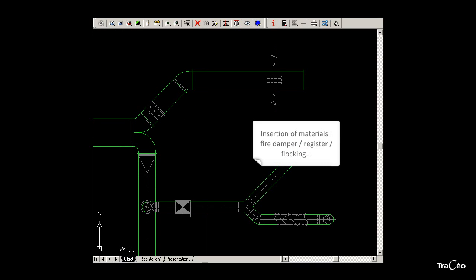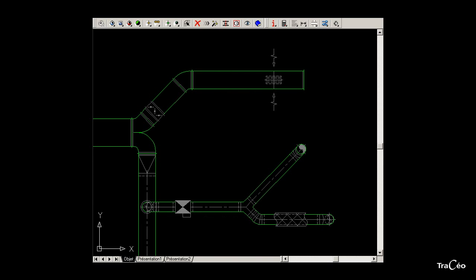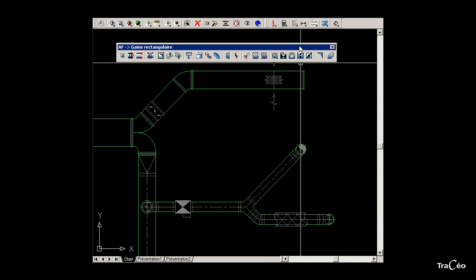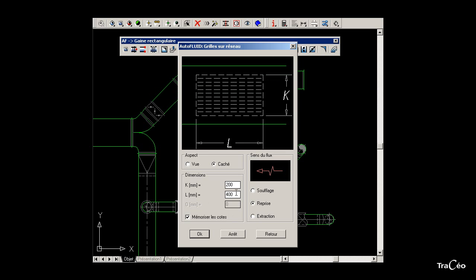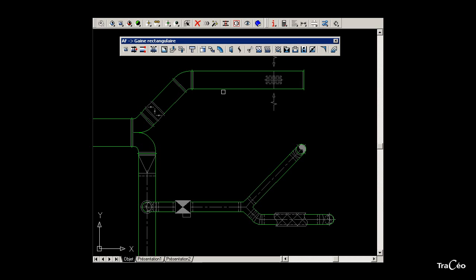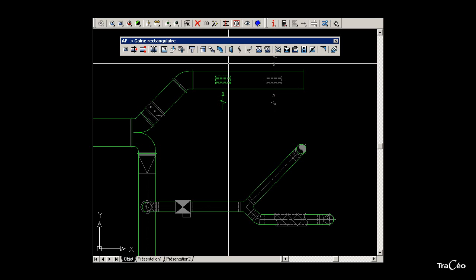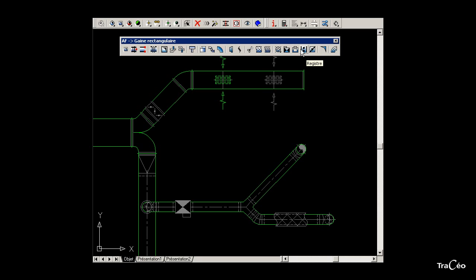To add equipment or insulation to an existing duct, use the toolbar related to the duct. For a rectangular duct, use the rectangular duct toolbar — right-click to call it. Use the register command and select square or rectangular register. Specify the register's dimensions and click OK, then select the duct. Click a first point to indicate the distance between the register and the arrows; each subsequent click draws a new arrow. Click to confirm and the command is over. For the damper, find the register command in the rectangular duct toolbar. Select the duct and the damper will appear.